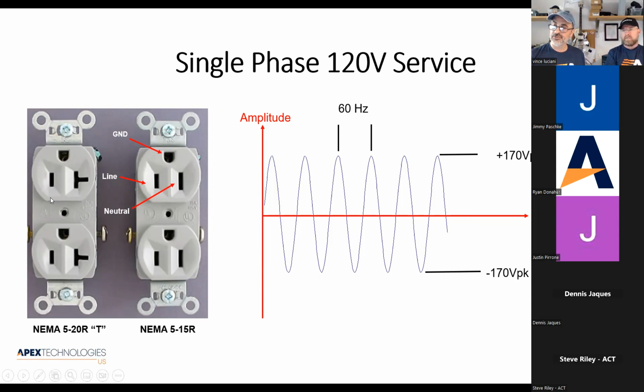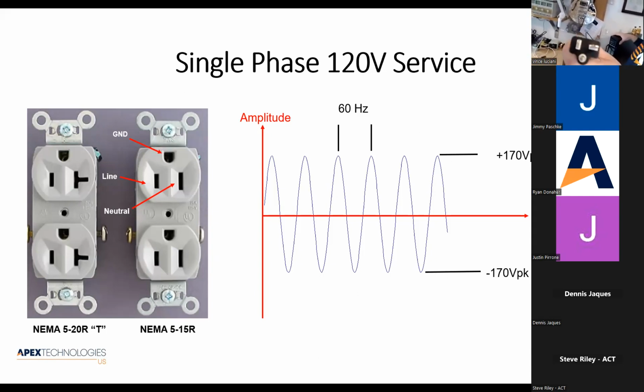On the other side, you can see a 20 amp, a true 5-20 outlet. The hot would be vertical, as you see here, and the neutral line is actually horizontal if you have a 20 amp load. And I think we have, like, this UPS is a 20 amp UPS, and this presents a lot of frustration for our dealers when they order a 20 amp product. It's going to come with the plug horizontal. I don't know if everybody can see that there. Here it's a little closer look. You see how that is? So that would only plug into a 20 amp outlet.